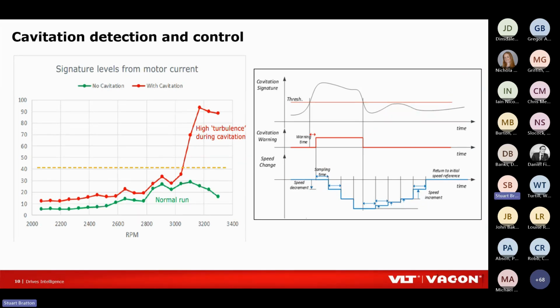Because we are able to analyze the signature, let's say, of the current that's going out to the motor, this also gives us the ability to detect cavitation in a pump. So if you were to run a pump across a range of speeds with absolutely no cavitation, we would get a particular, I'm going to call it, signature of the current.